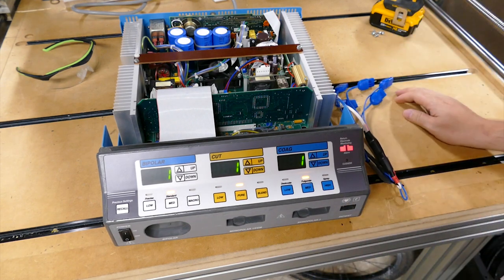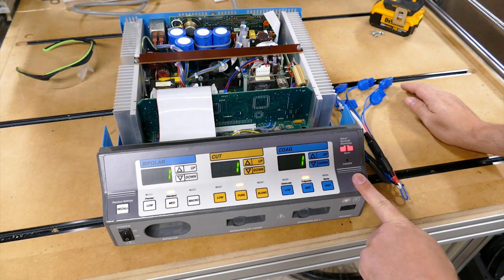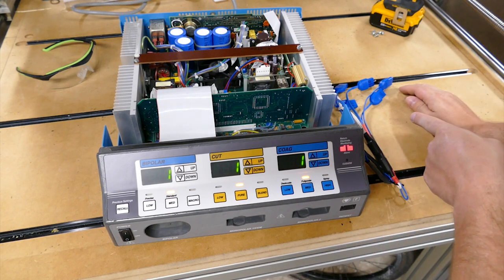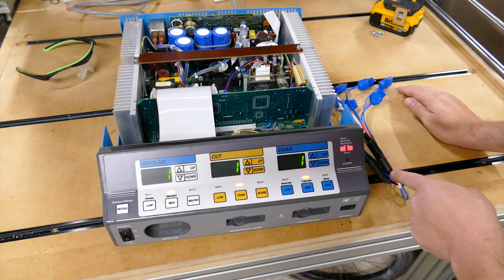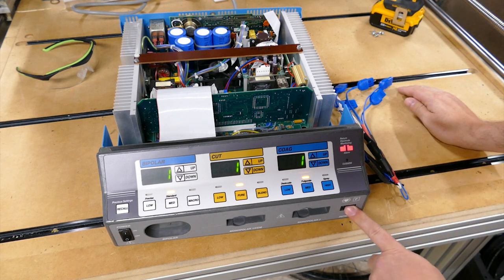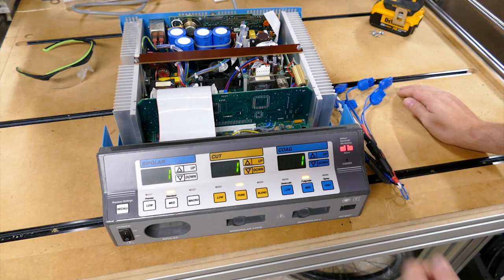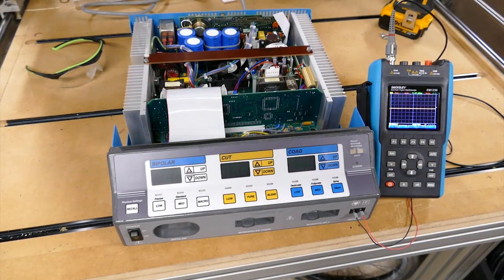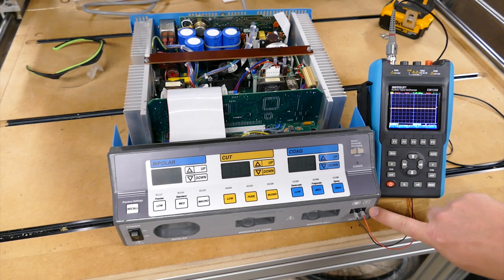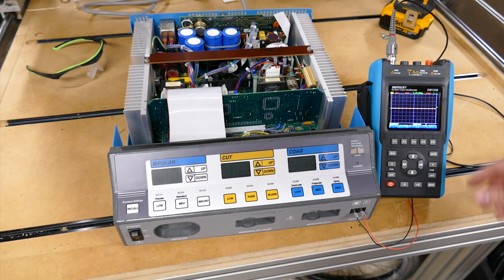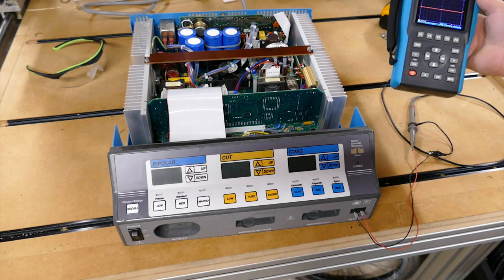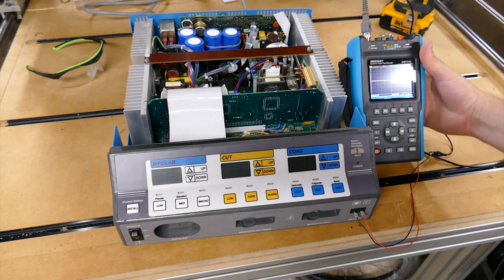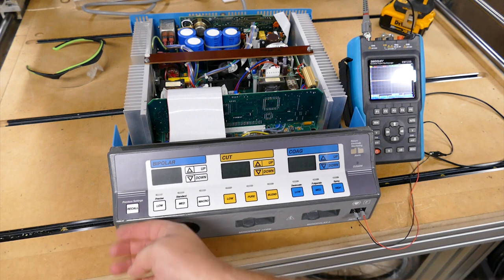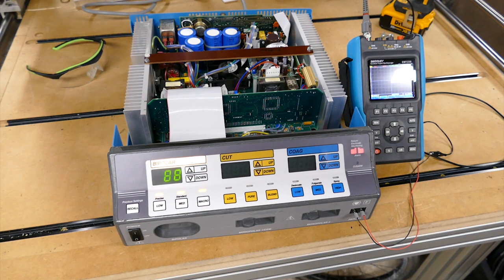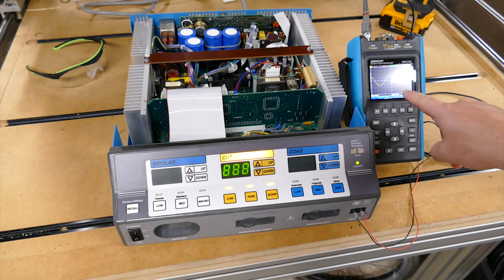So I'm gonna show you guys how to calibrate this unit right here using 10 ohm, 70 ohm, and 135 ohm resistors on this port. And we're also going to use an oscilloscope. So let's go ahead and set that up now. The first thing we need to do is hook up the oscilloscope to the patient return electrode connector. You can see I've just got it coiled around and connected over to my probe. Next thing we need to do is turn on the unit. You can see the oscilloscope is finding a signal.